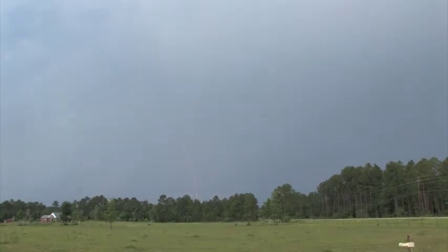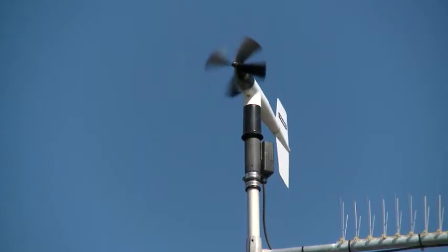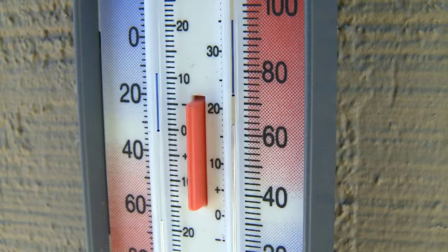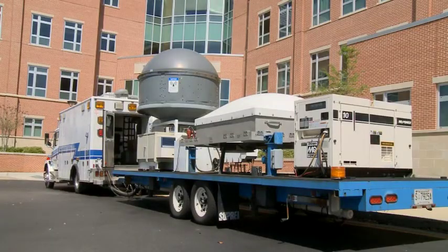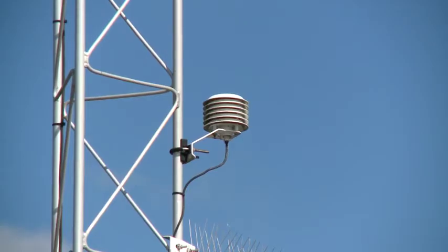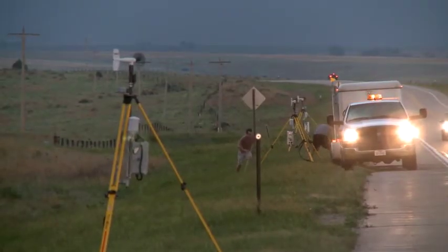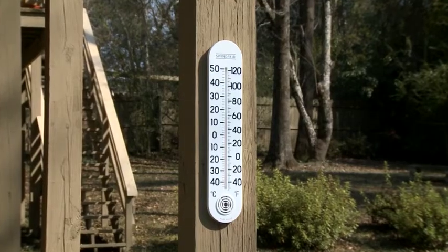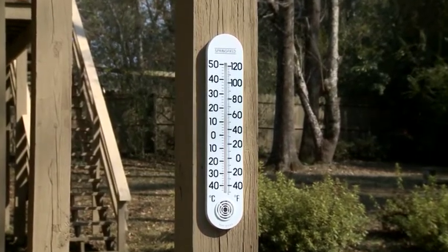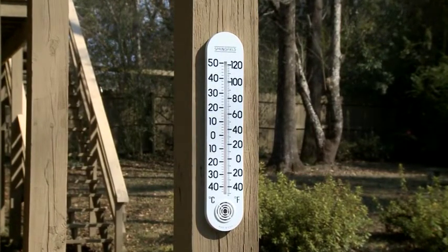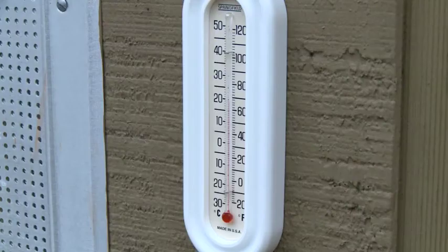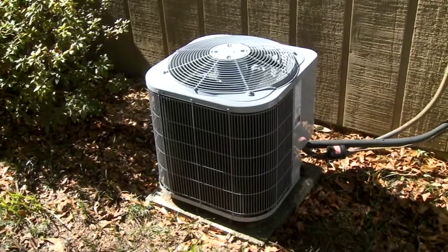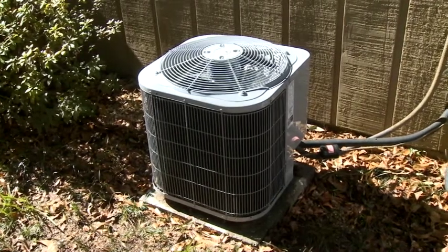Weather instruments are an extension of our senses. They have the benefit of being objective and consistent. However, all weather instruments must be calibrated, maintained, and properly positioned to avoid contamination of the data. For example, a basic home outdoor thermometer in direct sunlight will show a reading too high. A thermometer mounted on the outside of a wall will pick up some of the building's temperature rather than just the air temperature. If a thermometer is placed too close to an air conditioning unit, there will certainly be false readings of air temperature.